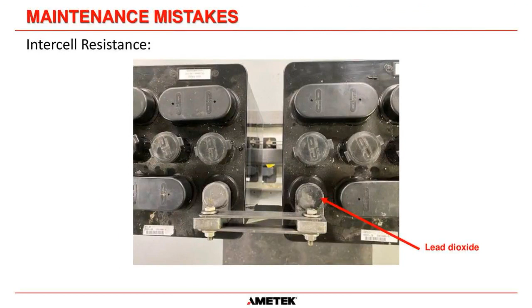Additional factors, here it is. You can see there is a design margin, based on the engineer's judgment. You might think they're going to add some loads to the system down the line, or want some kind of margin added in, so you can include that, and then the aging factor can be added as well. So you're absolutely correct, there is no standard on that. IEEE does have some recommendations, but remember those are just recommendations. You have to decide that for yourself, and in truth your plant procedures should give you some idea of what you should be doing. Hopefully that answered your question, George.